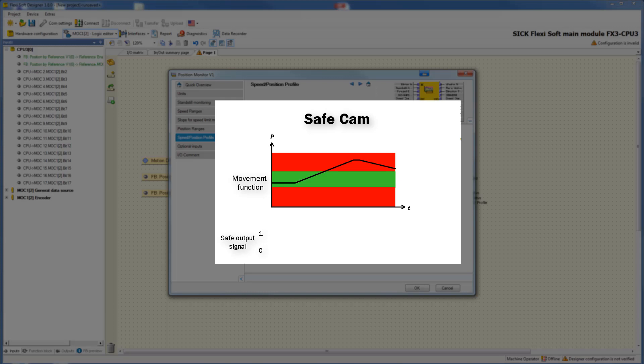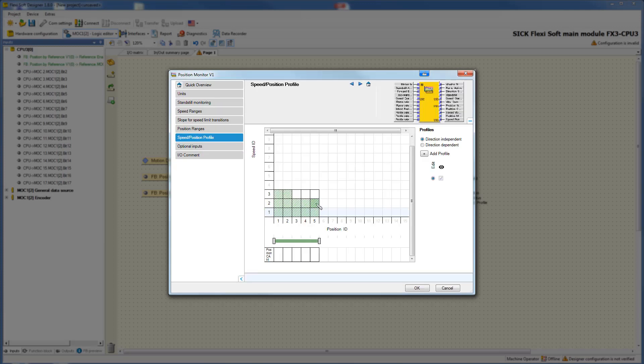The safe cam function realizes safe monitoring of the maximum and minimum position. If the drive is within the limits, the safety function generates a valid bit of 1. If the limits are exceeded, an invalid bit of 0 is generated. To realize the safety function safe cam, the output position cam can be defined individually for each position range in each speed position profile. This output can be used to implement electronic cams.